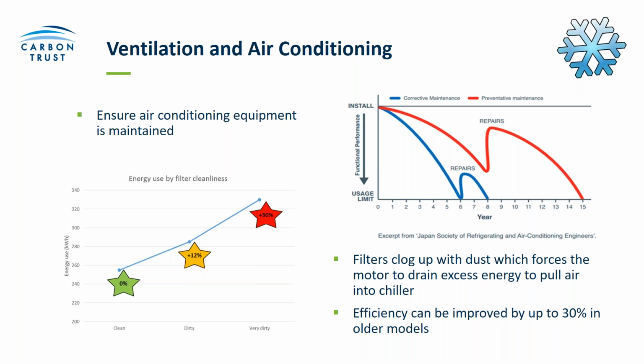The graph at the bottom shows the importance of filter cleanliness. Filters clog up with dust and use more energy. The red star shows that a dirty filter system can use 30% extra energy. The energy use shown goes from 0% up to an extra 12% if it's somewhat dirty, and up to 30% if very dirty. So just cleaning those filters can bring you back down to the most optimum energy use.